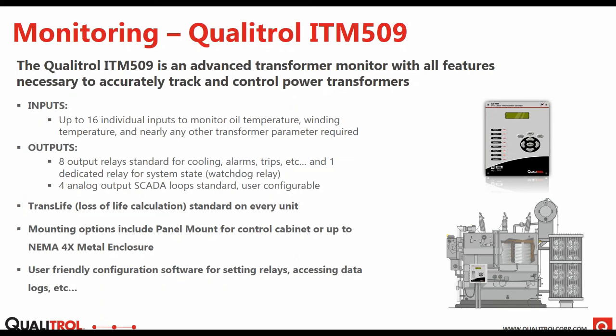So first here we have our Qualitrol ITM 509. It's an intelligent transformer monitor. And this can bring in all of the same signals that you would currently have on your transformer with just switch functions. So top oil, winding temperature, you can take in your liquid level, your pressure, and all of those, and you can bring them into one central location and communicate that out. So that's a great upgrade for a critical transformer or an aging asset where it could be a potential hazard or anything like that, where you're currently only getting an alarm contact or not getting any contact or not getting any remote communication at all. The 509 can bring in all of that information and communicate that out over numerous different protocols and communication styles.